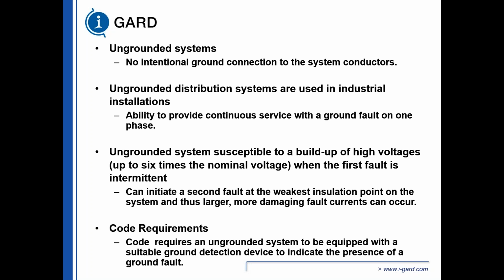Ungrounded distribution systems are used in industrial installations where people believe that they definitely cannot tolerate any interruption of any kind. They're susceptible to buildup of high voltages, up to 6 to 8 times, on an intermittent sputtering arc flash. And I'll show you a slide on how that's done. The code requires that ungrounded systems be equipped with suitable ground detectors. There is no ground fault protection with an ungrounded system. There's only ground fault detection.